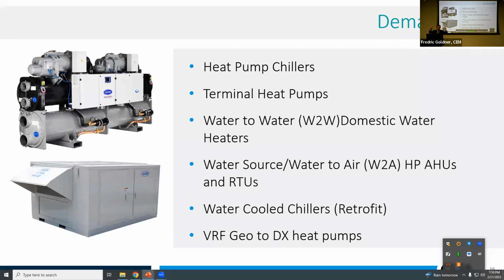VRFs with the refrigerant. That's the gambit. That's the win for geo, because in a retrofit, it's easier to install line set than it is supply and return rigid piping. And that's why these mini splits and ductless splits are all the rage, because it's just soft copper tubing. The geo compressor is the big module. It's in your machine room. It's connected to the earth. And then after that, it's just refrigerant line set to a branch box to all the heads.